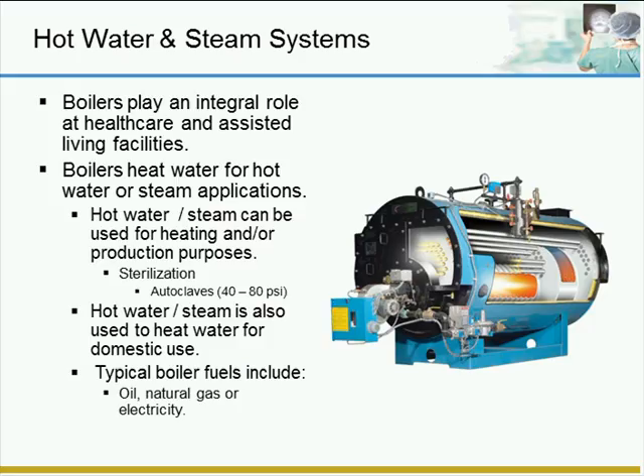Start off here with your hot water and steam systems. Hot water and steam systems play an integral role at medical facilities. Boilers are used to heat water for hot water and steam systems. The hot water and steam systems are used for comfort heating, sterilization, sanitation, as well as many other uses. High-pressure boilers are commonly found in central heating plants and are classified by the type of construction. You have water tube boilers, fire tube boilers, and smaller units will be cast iron.